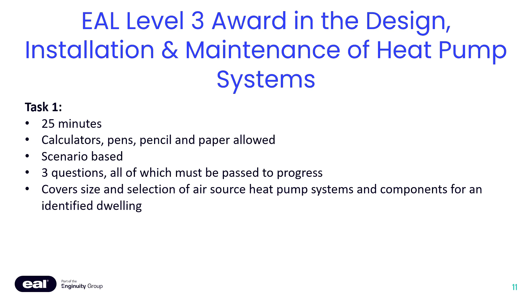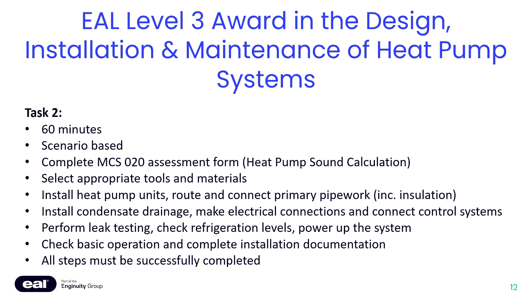So task 2 is the install, 60 minutes, scenario based again. The learner will complete the MCS 020 assessment form, the heat pump sound calculation. They will select appropriate tools and materials. They will install the heat pump unit, route and connect primary pipework, including the insulation. Install the condensate drainage, make electrical connections and connect control systems. They will perform leak testing, check refrigeration levels, power up the system, and then check the basic operation and complete the installation documentation. All steps must be successfully completed.